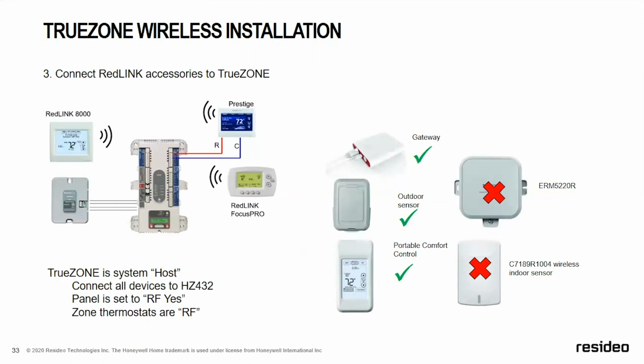So red link zoning, the things we can and cannot use. If we have a THM 4000, we can use an outdoor sensor, the portable comfort control, or a gateway. At this time, we cannot use an equipment remote module. We cannot use wireless indoor sensors. Now that's with wireless red link. That's not to say that if you're using an EIM board, you can use a wireless indoor sensor. There are different applications, and we'll go over that in next week's training.